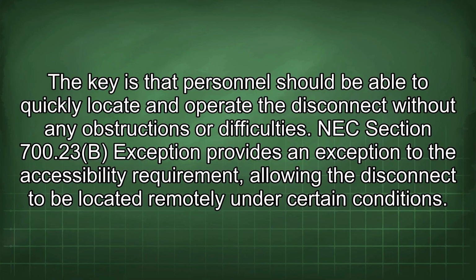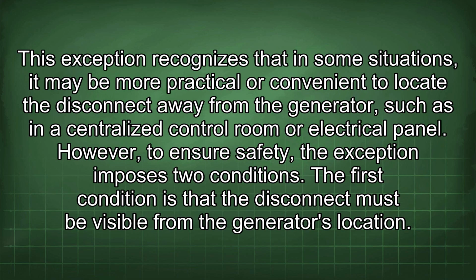NEC section 700.23b exception provides an exception to the accessibility requirement, allowing the disconnect to be located remotely under certain conditions. This exception recognizes that in some situations, it may be more practical or convenient to locate the disconnect away from the generator, such as in a centralized control room or electrical panel. However, to ensure safety, the exception imposes two conditions. The first condition is that the disconnect must be visible from the generator's location.